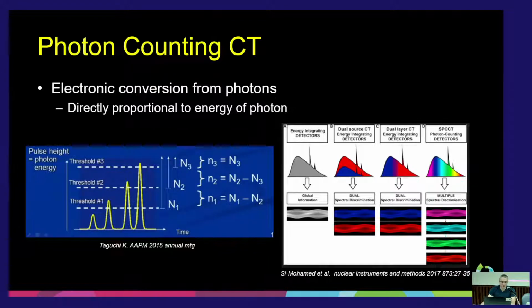They're obviously polychromatic. There's multiple energies in here. If you could somehow condense all of that into one single vertical line, an image with a monoenergetic at 40 keV, or any one of those energies, that's the type of energy you would see in those virtual monoenergetics. And so really what it's doing is, because of the way it reconstructs it, it can manipulate the contrast and the noise in the image to be associated with a specific energy along the Bremsstrahlung curve. Basically, it's just pure math to get those different looks.